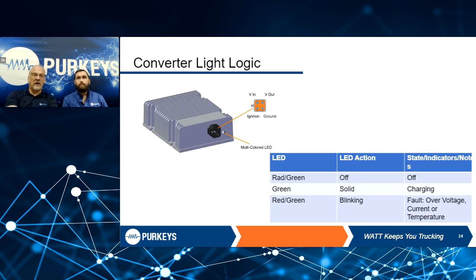We've got two different converters you'll see out there. One is this 4-pin module we changed right around 2021, the updated one, which has basically one LED indicator. It'll alternate red and green when the system is off, solid green means I'm charging, and red-green flashing means I've got a fault in there, be it over temperature or other issues.